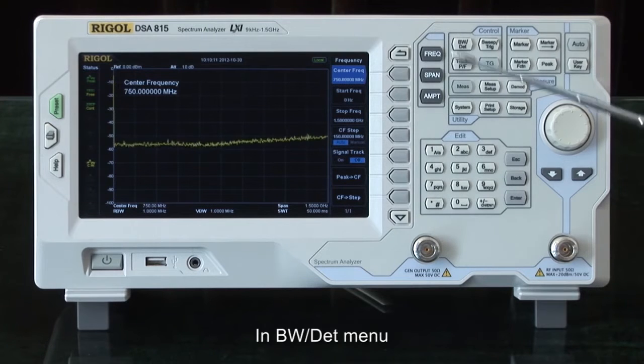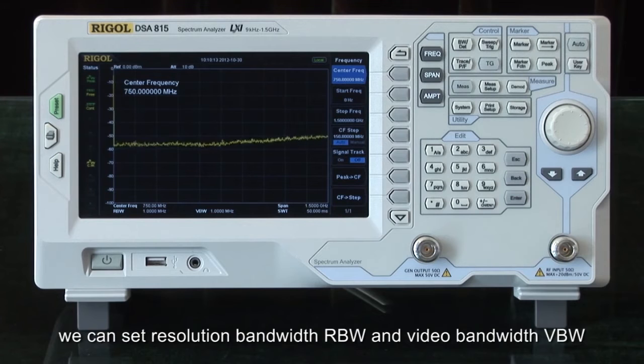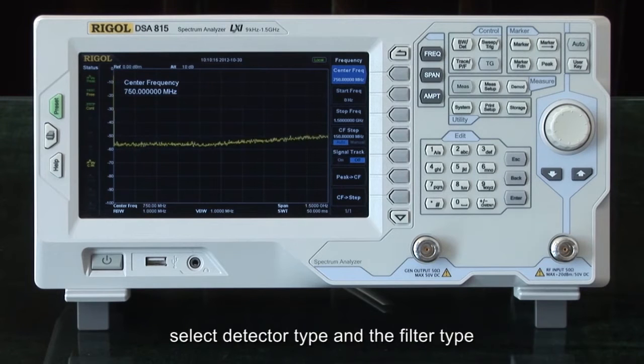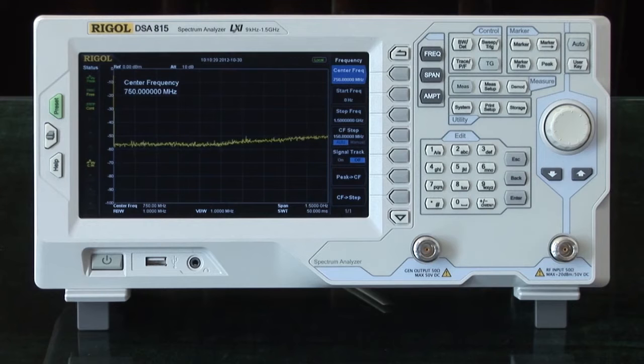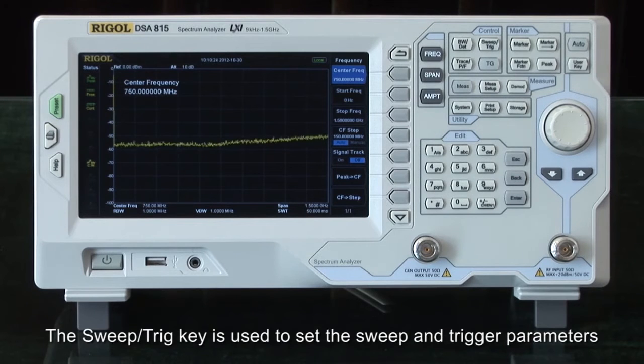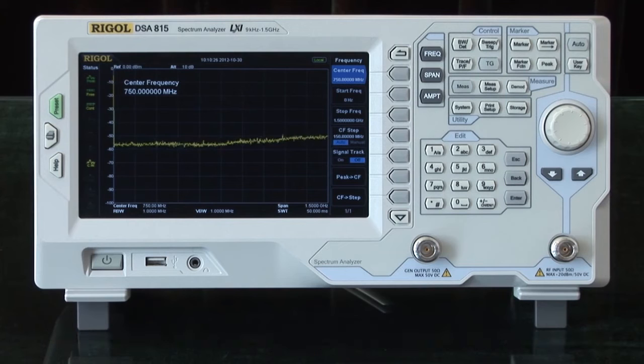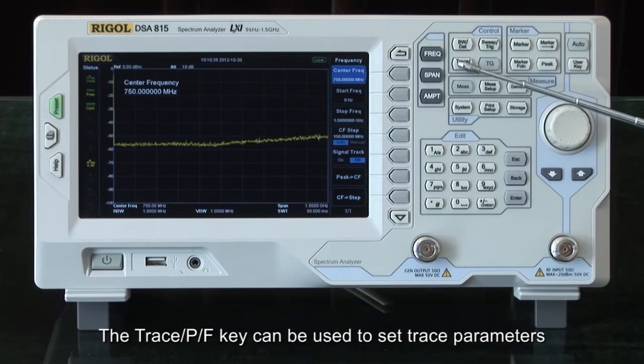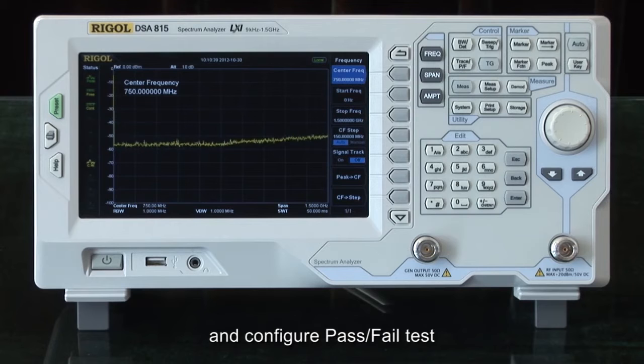In the bandwidth detector menu, we can set resolution bandwidth and video bandwidth, as well as select the detector type and the filter type. The sweep trig key is used to set the sweep and trigger parameters. The trace pass-fail key can be used to set trace parameters and configure the pass-fail testing.